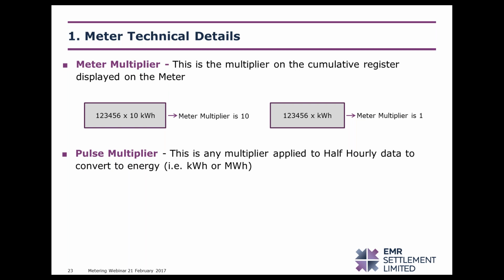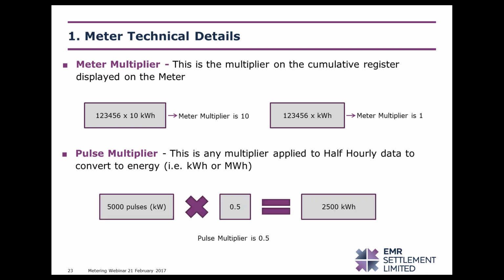The pulse multiplier is any multiplier that is applied by a data collection system to convert half-hourly data recorded to an energy format. So in this example, the meter half-hourly channel has recorded 5,000 pulses, and that is related to kilowatts and not kilowatt hours. The data collection system would multiply that raw pulse value by 0.5 to convert to energy, to give an energy value of 2,500 kilowatt hours. The metering statement in this instance would state that the pulse multiplier is 0.5. In a lot of modern meters, the pulse multiplier is 1. This is something that should be confirmed by the installer or the manufacturer of the meter.